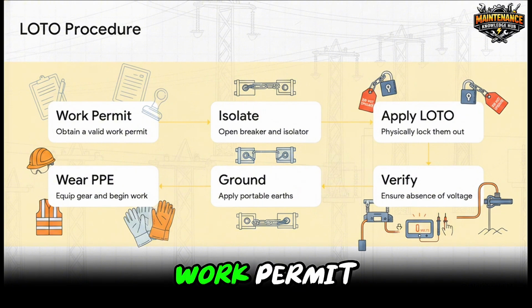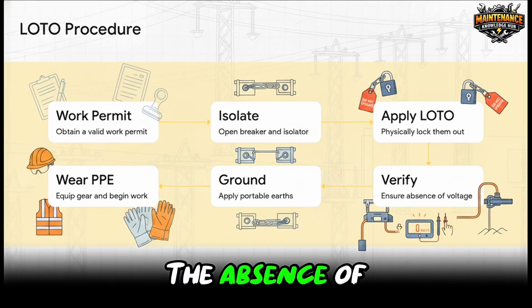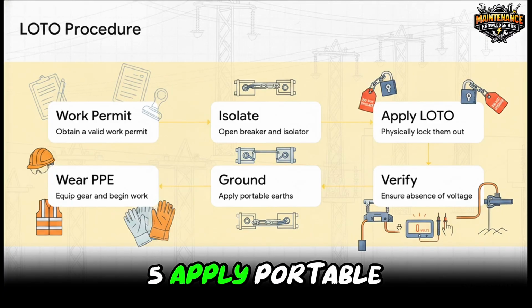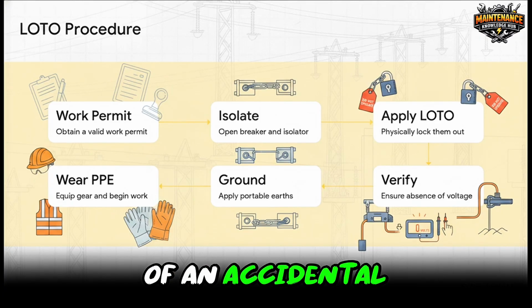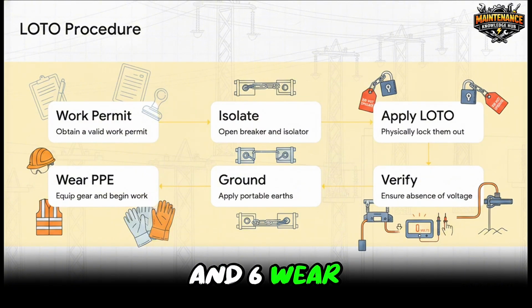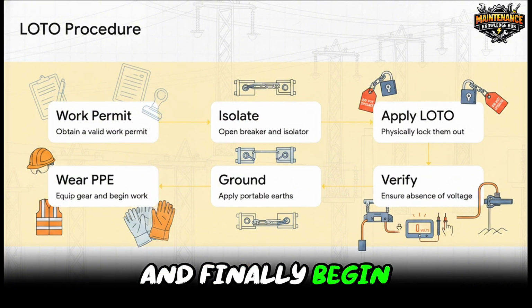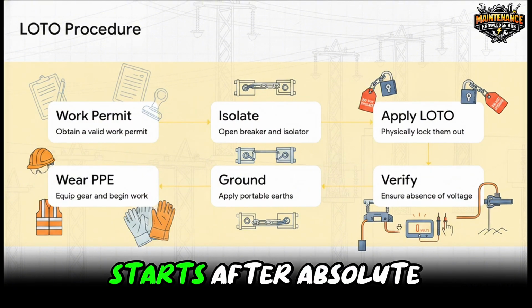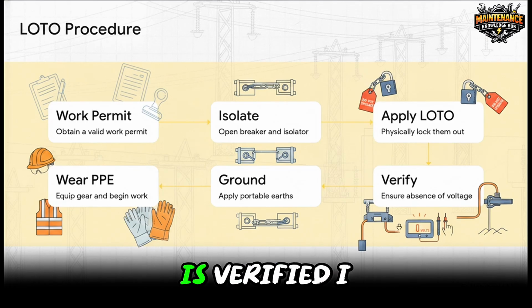1. Obtain a work permit. 2. Isolate the equipment. 3. Apply your LOTO. 4. Actively verify the absence of voltage. 5. Apply portable earths just in case of an accidental re-energization. And 6. Wear your appropriate PPE and finally begin work. Hands-on work only ever starts after absolute safety clearance is verified.